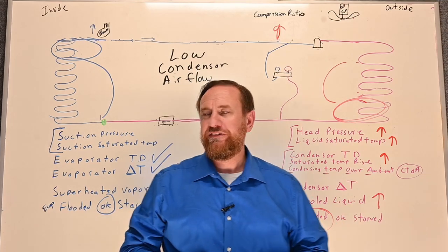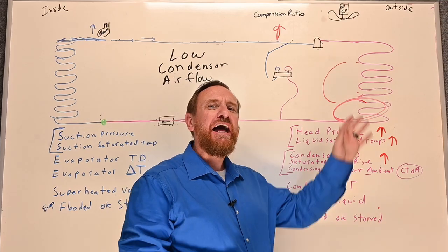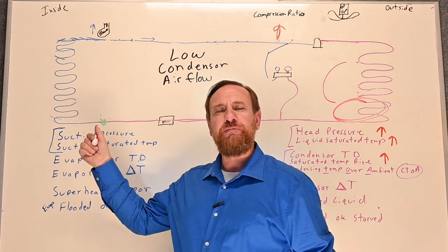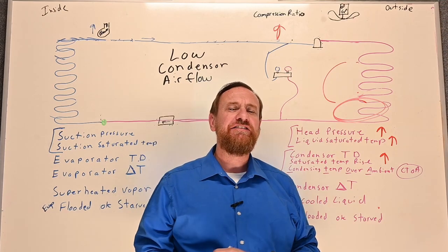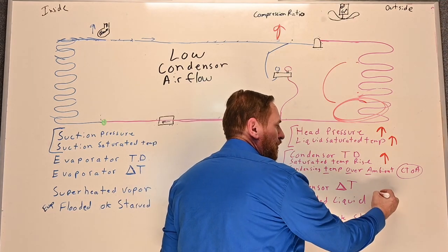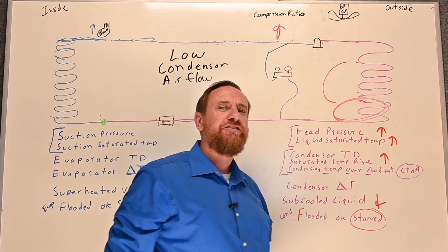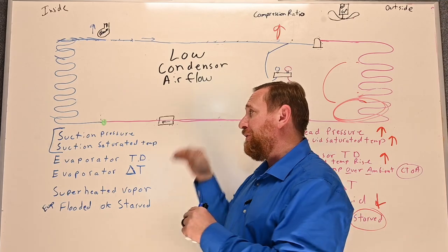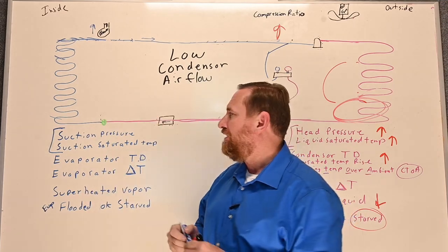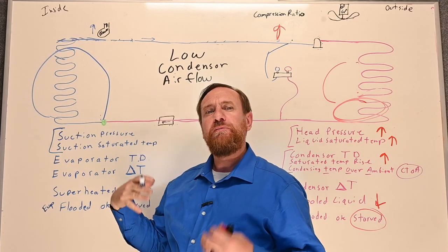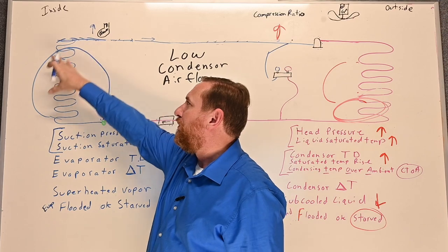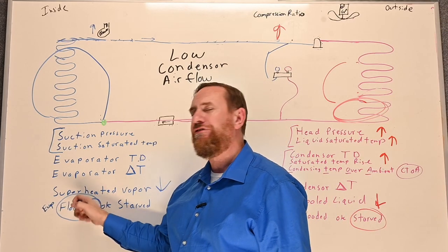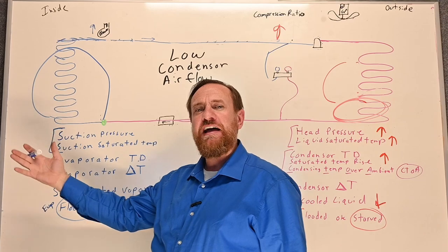With a fixed orifice, things change. We have higher pressure on the outside, which means there's more pressure pushing against the liquid through that same fixed orifice — we're pushing harder. We could actually see our sub-cooled liquid start to drop, which can give us a starved condenser as we push liquid out at a much faster rate. That liquid is being pushed through the metering device at a faster rate, so we end up with more liquid in our evaporator coil, which means less superheated vapor. Our superheat starts to drop and we end up flooding the evaporator coil — too much refrigerant in there.